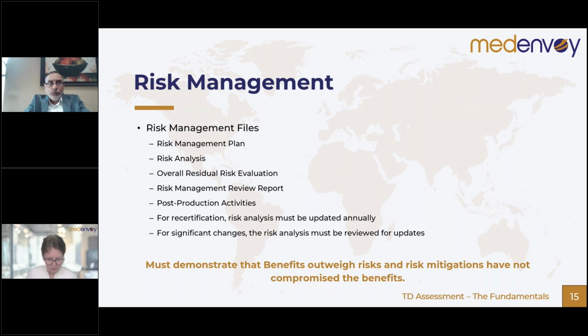So one of the points that we are trying to ensure is that during your risk assessment, risk identification or risk control, if you identified or chose a risk control or mitigation, we have to demonstrate that my mitigation has not compromised the benefit. So notified bodies now expect to see in your risk documentation that when you implemented a risk control for a specific hazard, you did not compromise the benefit. So it should be visibly demonstrated that after implementing the risk control or mitigation, benefit was not compromised. So that is a very important point.